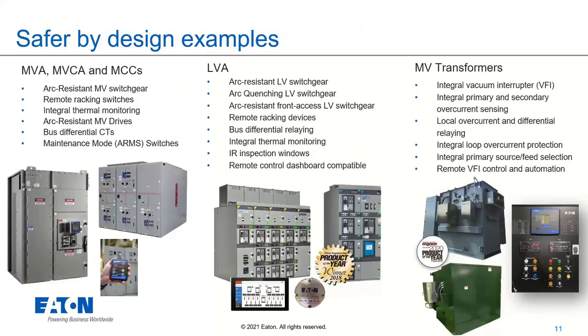So just a few examples. These are some Eaton products, but you can find very similar stuff throughout the industry. Medium voltage, in the control assembly world or the motor control center world, you're obviously going to have your arc resistant MV switchgear. You're going to have remote racking, thermal monitoring. In the LVA world, low voltage assemblies, we're now seeing, in addition to the arc resistant, something arc quenching, where you're actually essentially creating bolted faults to quench that, to remove that fault from the scenario. They're doing very similar stuff as MV, those remote racking and thermal monitoring as well. But you also see some remote dashboards and things like that for interfacing with your products.